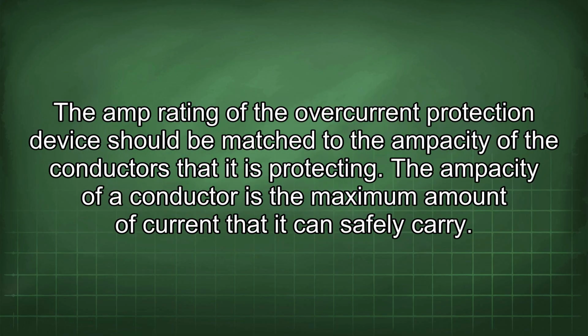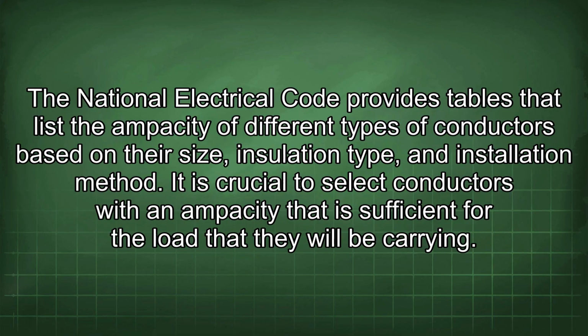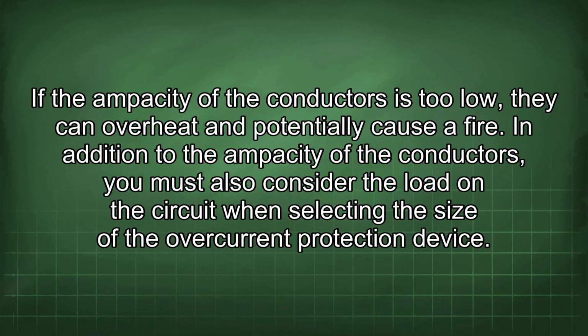The amp rating of the overcurrent protection device should be matched to the ampacity of the conductors that it is protecting. The ampacity of a conductor is the maximum amount of current that it can safely carry. The National Electrical Code provides tables that list the ampacity of different types of conductors based on their size, insulation type, and installation method. It is crucial to select conductors with an ampacity that is sufficient for the load that they will be carrying. If the ampacity of the conductors is too low, they can overheat and potentially cause a fire.